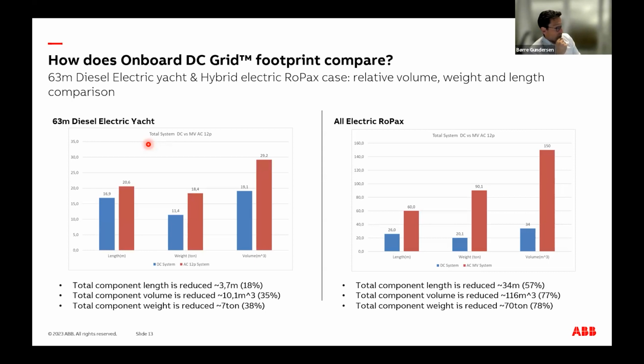Then, of course, the extreme case, which I'm almost a bit embarrassed to show because it doesn't seem to be true, but there's a lot of savings there. This is a special vessel, all electric battery, but that's where it really fits well, so I wanted to show it. The component length is reduced, in this particular case a big vessel, by 34 meters of switchboard and transformers, 57% of equipment in length. The volume was reduced even more, by 77%.